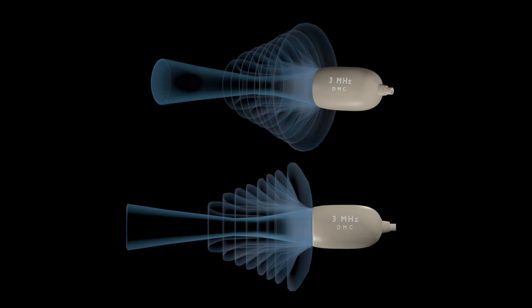So I found these images through Radiopaedia, a great resource for ultrasound-related findings and artifacts. And this shows a good 3D representation of these side lobes. They reflect outward from the central beam. And as the ultrasound crystals expand and contract, the primary beam goes in the direction that it's supposed to, with these secondary beams radiating in a circular fashion outward.